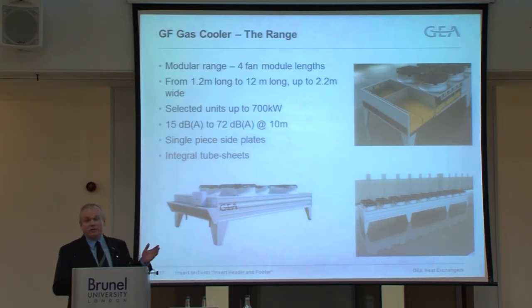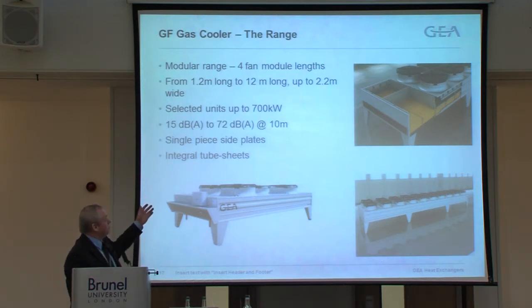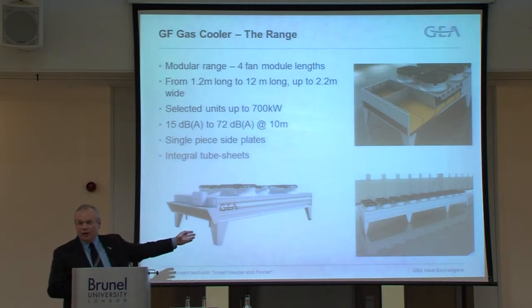I'm going to talk about the features of the product: a gas cooler, 4 fan modules, modular design throughout. We have a unit that goes from 1.2 metres through to 12 metres long. We're selecting gas coolers up to 700 kilowatts, from 15 dBA to 72 dBA at 10 metres. The unit is based on our standard RF air-cooled condensers.